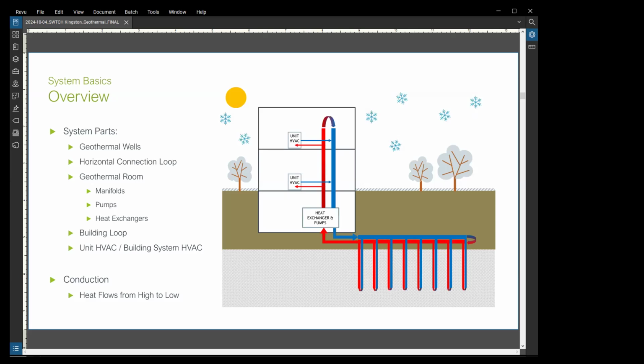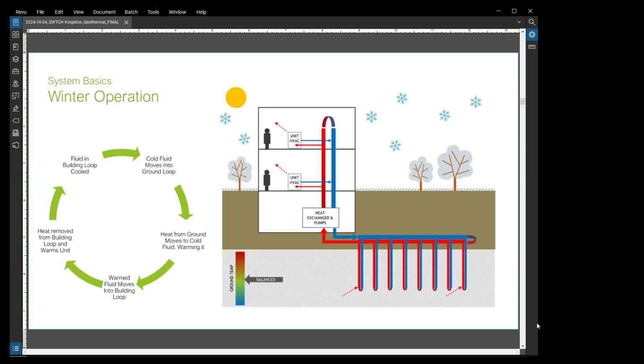The building loop then is connected to the individual units that are in each residential unit or space. So these could be heat pumps, these could be fan coils, these could be VRFs. It really depends on the overall design of the building, but the idea is that the supply fluid is coming in at one temperature. The heat from that fluid is either extracted, or the heat from that air or from that room is put back into the fluid, and then it goes back down into the ground loop where it cycles through and switches over. And it's just essentially running through that cycle again and again and again. So trying to put it into simple visuals.